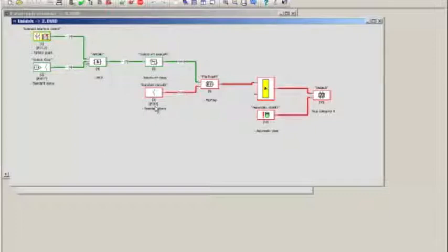So all I need to do is turn that signal true, and again, I could do that from a PLC or by virtue of a button that I locate next to the door. When I provide 24 volts to this input, then the set will be true, and because the hold is already true, everything here, the flip-flop, will turn true, which will power OSSD to the output and therefore unlatch the door. So let me do that. I activate, and now I can open the door.